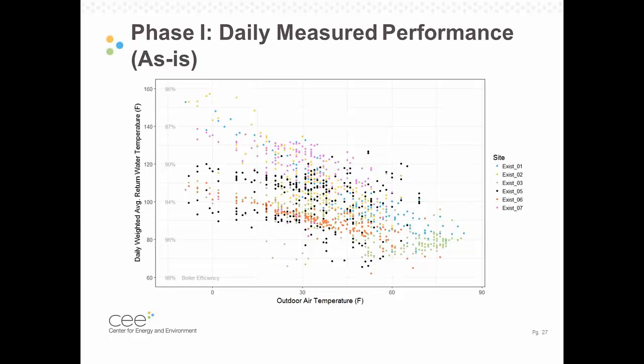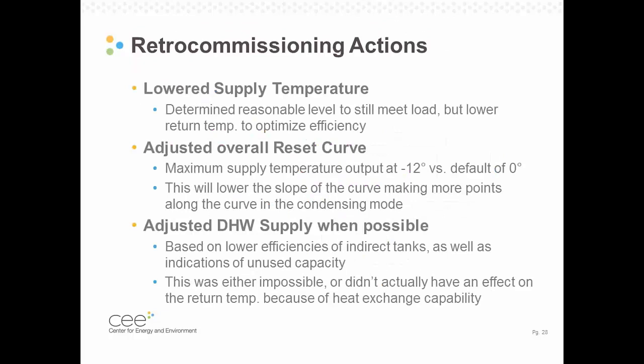So you can also see, based on that curve that Becky showed earlier, what the approximate efficiencies were at those return water temperatures, ranging from about 94% at 100 degrees up to 87% efficient at 140 degrees, and then dropping off from there. So those 3 factors really gave us those low return water temperatures that we were targeting, and therefore the high system efficiencies. So despite these high system efficiencies, we still wanted to see if retrocommissioning yielded any improvements.